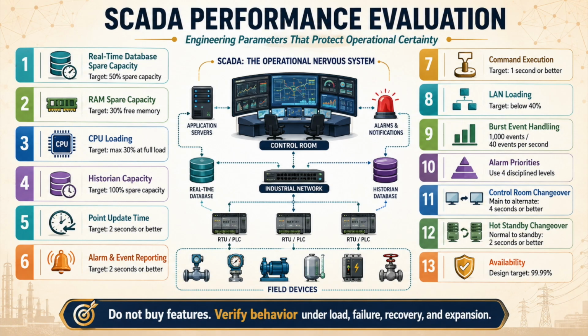So failure mode testing must pull cables, fail servers, isolate networks, restart services, overload alarms, break communication links, restore backups, recover failed nodes, and verify that operators retain visibility, authority, alarm awareness, historian continuity, and confidence. This is where design engineers must become strict, because words such as scalable, reliable, robust, redundant, high performance, and future-ready have no engineering meaning until they are converted into measurable behavior.